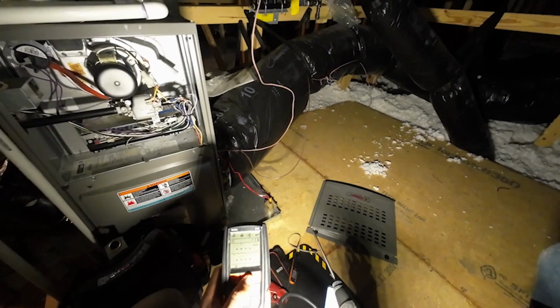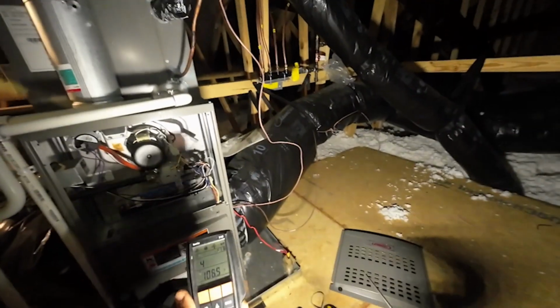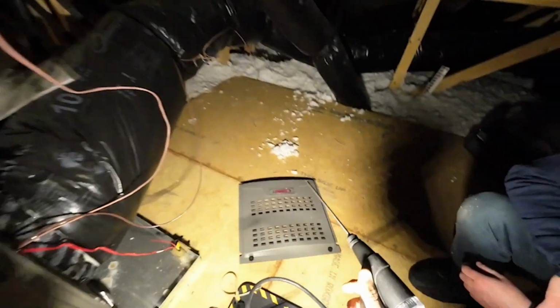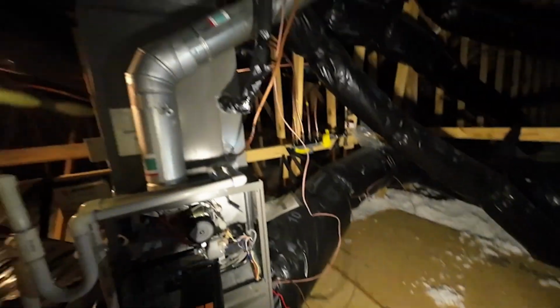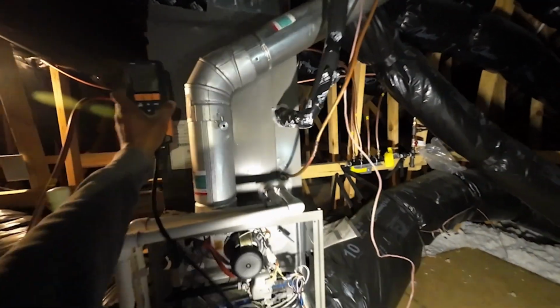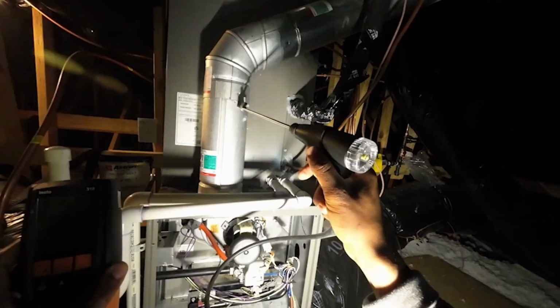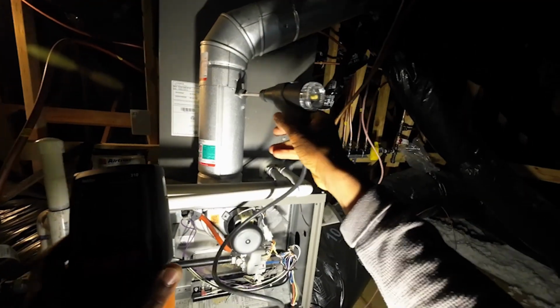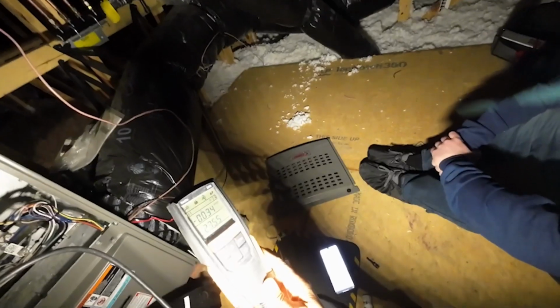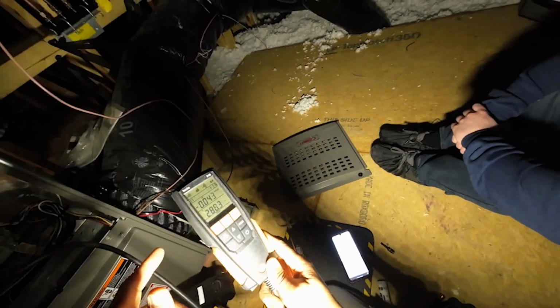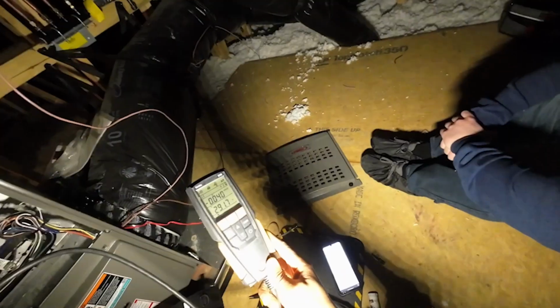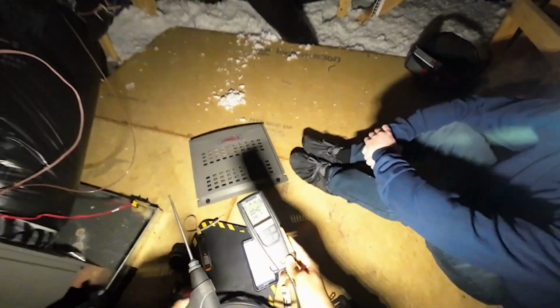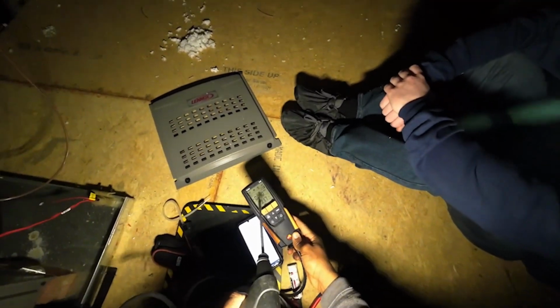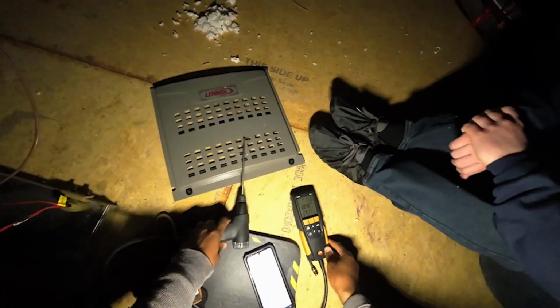So we're just going to go ahead and hit start. We want to make sure our draft is probably between 2 and 3/100ths, maybe 2 and 4/100ths of an inch of water column. So we pop that in there like such. Always zero that to atmosphere, and we can see that's about, we'll hit stop and see where it stands, about 4/100ths of an inch of water column. That's a really good draft. Okay, and that's how you see 0.04. That's 4/100ths of an inch.